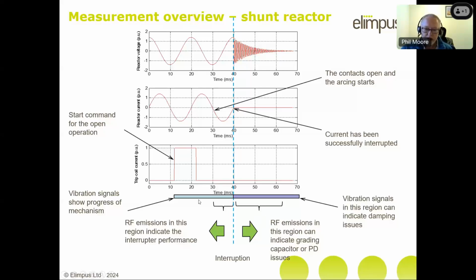And so we're measuring vibration. We measure the vibration all the way through, but from the trip signal to the point of current interruption, we're looking to see the progress of the mechanism. And from the interruption onwards, we would look to see whether there are any issues with the damping. Probably damping is slightly more relevant a little bit earlier on. In the part where the arc is burning, so when the contacts are open, which as we've said ideally occurs just a little bit after the zero crossing, the RF emissions tell us about what's happening in the interrupter, so it gives us an idea of how well that's performing. And once the arc has gone out, the RF emissions tell us about two things. They tell us about the grading capacitor, whether there's a problem with those, and secondly, whether there's a PD issue.